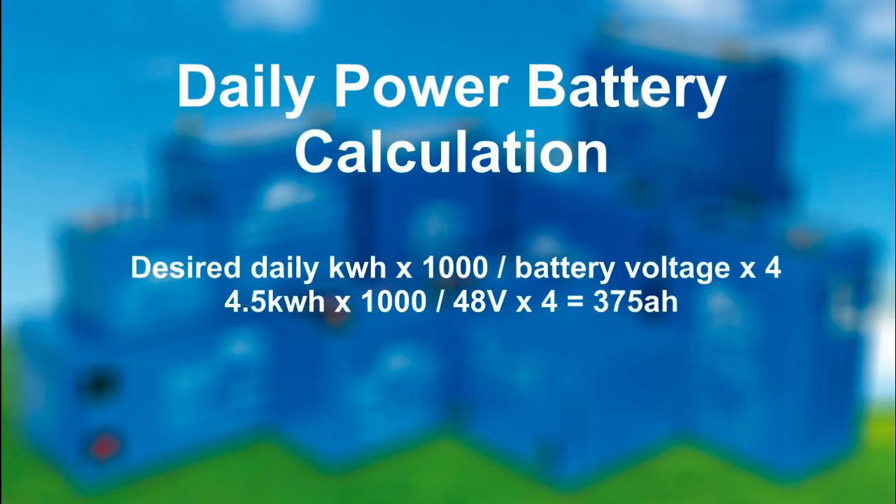That 375 amp hours is still below my 400 amp-hour battery bank capacity. Now, some people will say this formula is flawed, but the items in the calculation assume 24 hours of battery discharge. I typically get a minimum of eight hours of winter sun, which leaves only 16 hours of real battery consumption in the worst case — so the formula works for just about anyone. This formula is also why each morning I get up with the batteries usually discharged less than five percent. I left heavy usage items like water heaters and heat pumps completely out of my equations on purpose.